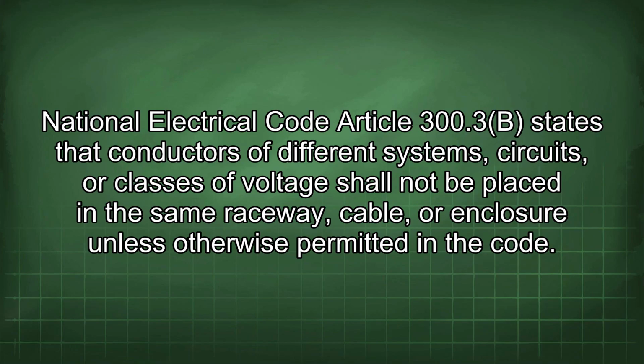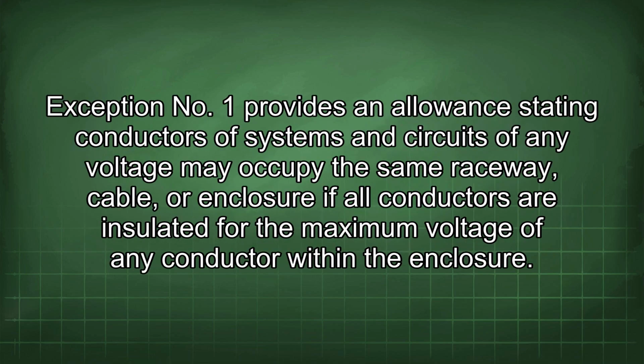National Electrical Code Article 300.3(b) states that conductors of different systems, circuits, or classes of voltage shall not be placed in the same raceway, cable, or enclosure unless otherwise permitted in the code. Exception No. 1 provides an allowance stating conductors of systems and circuits of any voltage may occupy the same raceway, cable, or enclosure if all conductors are insulated for the maximum voltage of any conductor within the enclosure.